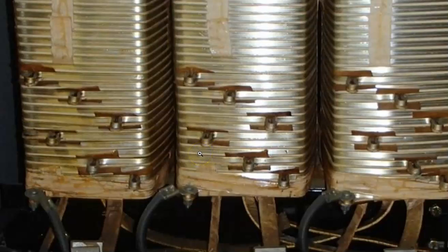I've run into it in the field before where people changed taps, and because the varnish is clear, they just assume electricity can pass through it, like electricity can see it or something. I don't know what's going on with those people, but whoever changed those taps left the varnish on there, and it cooked off the transformer. It was a crappy business trying to replace that transformer later on. Anyways, just make sure you're cleaning those taps off when you move them over.